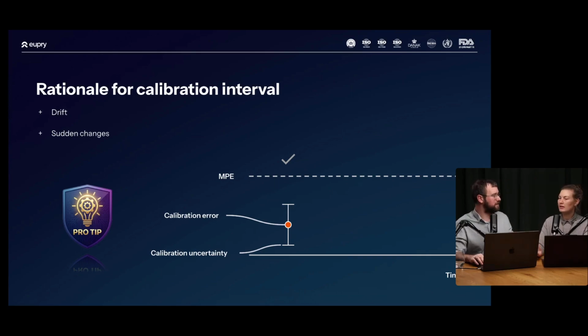How would you read anything about the drift in your calibration certificate? Often it's going to show in the data sheet. You're going to have it, and of course you can't say for that specific sensor what the drift is, because you would have to calibrate it, use it, and then calibrate it. But often the supplier is going to provide a small maximum drift, what the upper and lower limits for drift are.